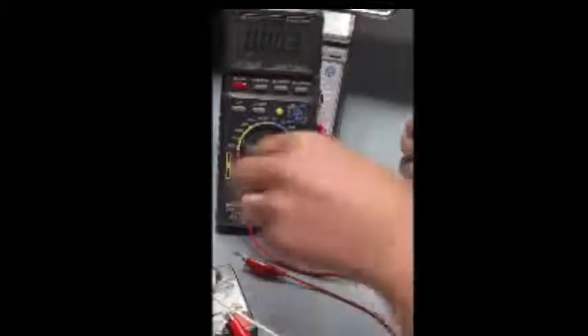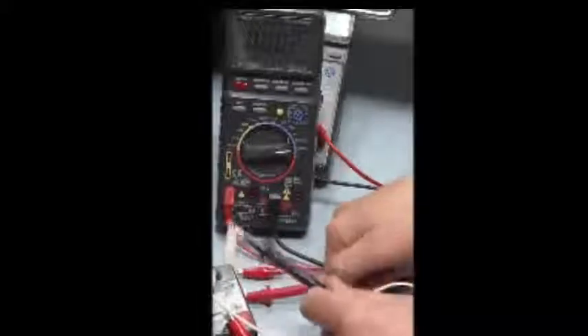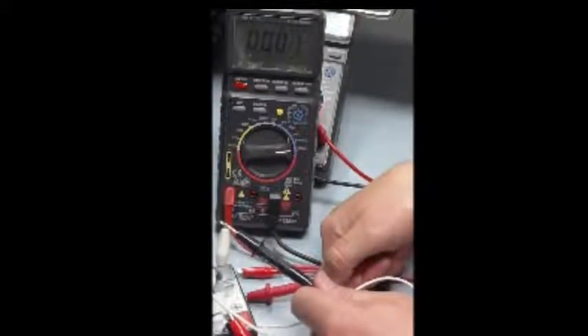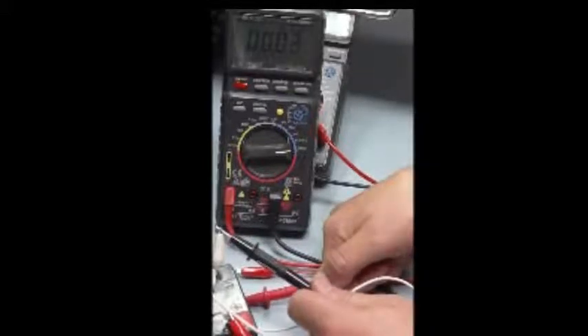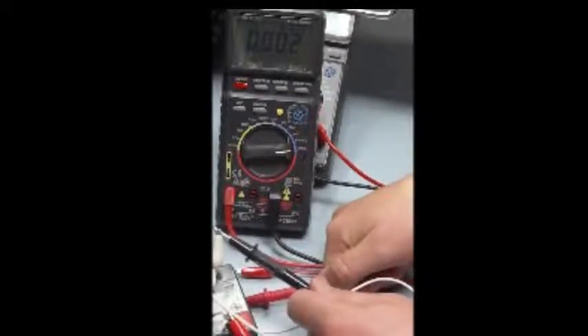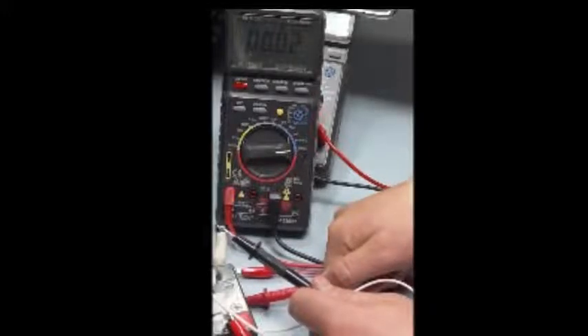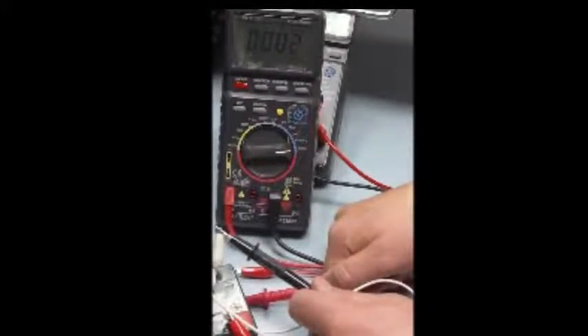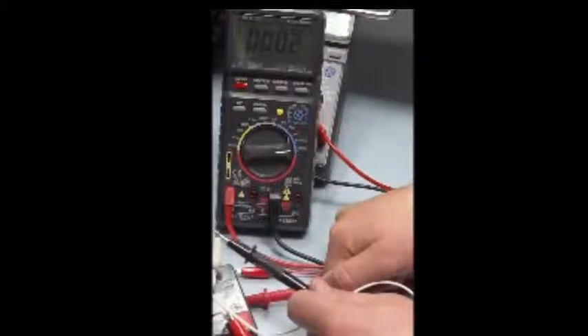Now let's just take a look at 0.55 of a milliamp. What if we had set our dial to the 20 amp range? Will it still read? Well, it could, but you can see that this needle is not moving because the range is set so high. What this could do for me is just tell me if I had a little more current, whether I had system present or not, whether I had flow of current. It's not in our best interest to always leave it set at 20 amps and then try to measure these lower values. That's not really what we want.